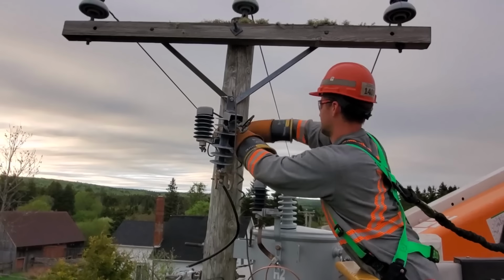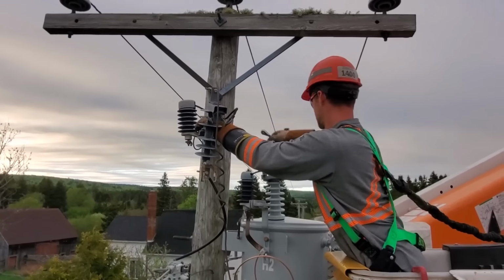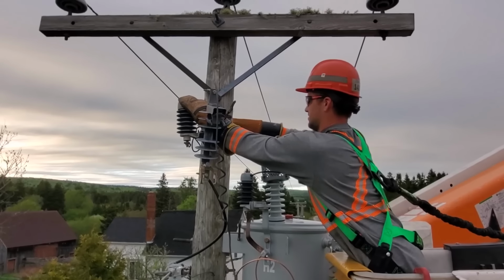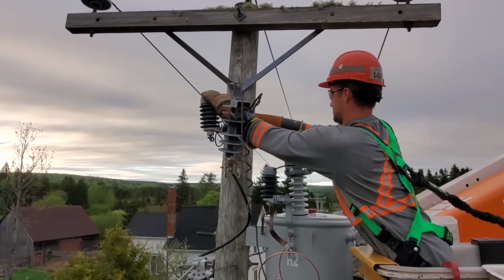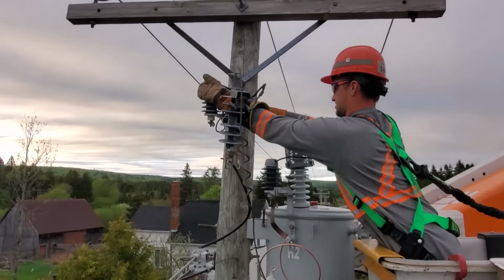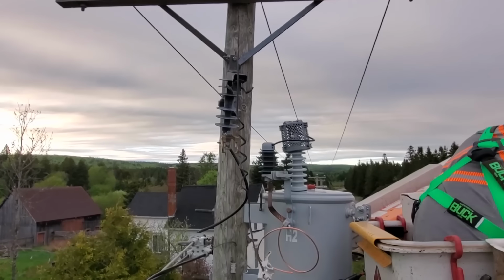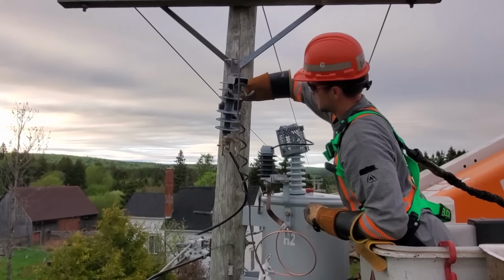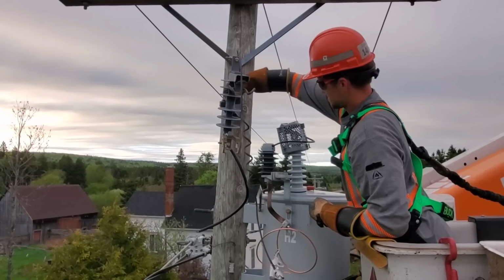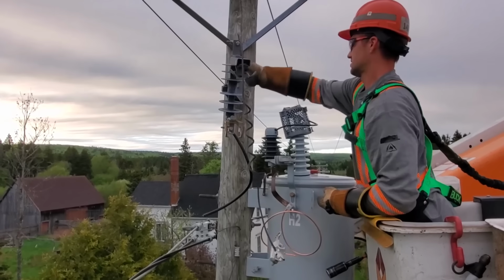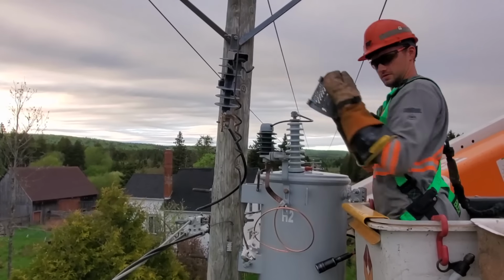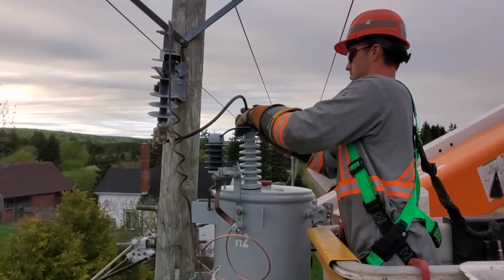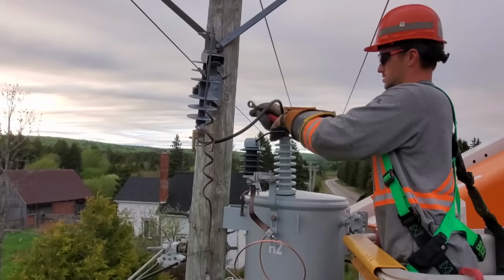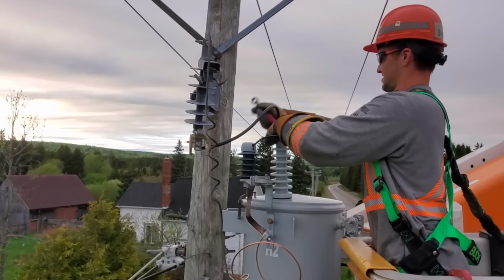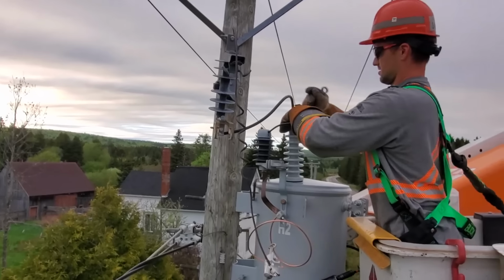And once you have a tool out, guys, try to do everything you can within that work zone with that tool. You notice he didn't take out his wrench until it was time to remove that lightning arrestor lead. Rather than putting it away, he continued on to use that to remove the lightning arrestor. And from here, you'll probably notice that he's going to hook that primary lead onto that bushing next while he still has that wrench out. That's just another style of a squirrel guard that we saw right there. He's also using a hand tool to tighten the primary in this case, so he doesn't risk over tightening that connector on the primary bushing and breaking it.